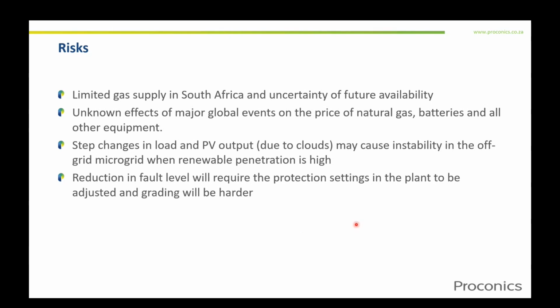Step changes in load, as well as PV output due to clouds, may cause instability in an off-grid microgrid when renewable penetration is high. You also get a reduction in fault level, which requires protection settings in the plant to be adjusted, making it harder to achieve proper protection grading.